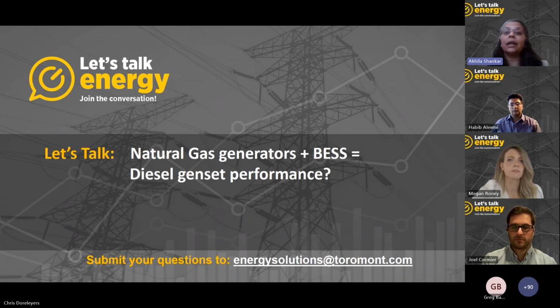Up until the introduction of the Caterpillar fast response natural gas gensets from the 750 kilowatt to the 2.5 megawatt ratings, the best performance some natural gas gensets in the market could achieve was only about 50% block load at one time. For the lean burn natural gas gensets, the block loading capability was much lower, in the range of 25 to 30%. Most lean burn units are actually optimized for utility parallel operation with only about 5 to 10% block load capability. But the Caterpillar fast response natural gas gensets can take 100% block load in one step and recover to rated values. They do start under 10 seconds as well.